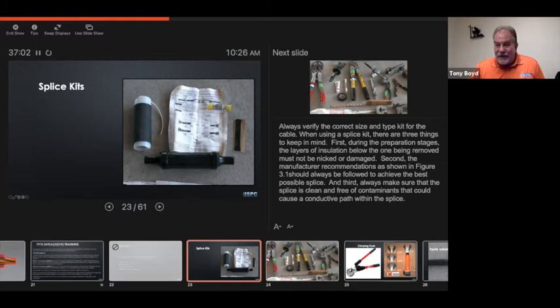This comes in the kit. This is also a type of water sealant. So you can see at the end of the cable where we have our concentrics, and we have the jacket. We took the concentrics back so we can add that extra water seal on there. This company also requires this to go over that splice body.